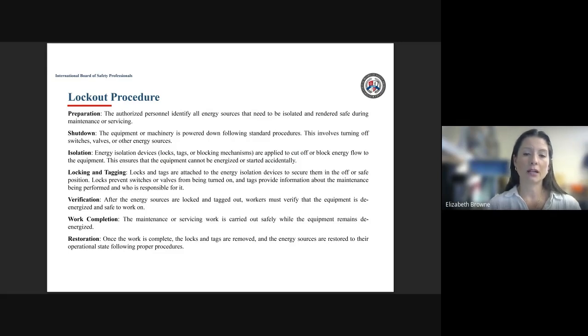Then we'll apply our locks and tags to every energy source, to make sure that it physically cannot be turned back on. And then again, like I said, we will verify the energy source is locked out. The workers must try to turn the equipment back on and ensure that it's de-energized and safe to work on. And then once that's the case, then maintenance, servicing, and repair may occur.